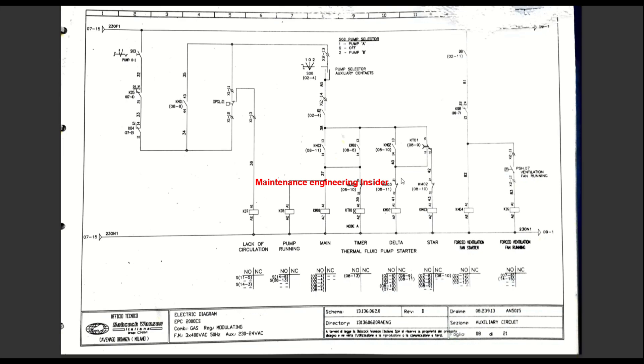The transition to delta is KM2. By then the latch has closed — KM1 latch has already closed to keep it running. Look at the timer as well: when KM1 is latched in, the timer is activated. This actuator here is the actuator of the timer. This is how we troubleshoot the star-delta sequence.